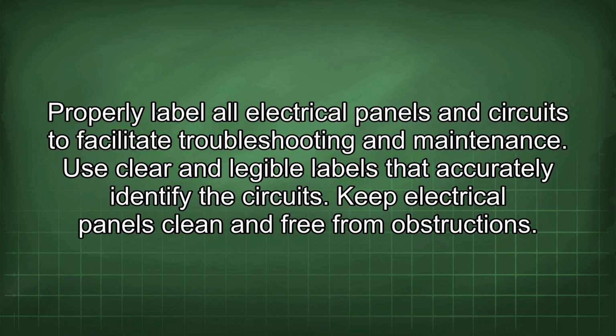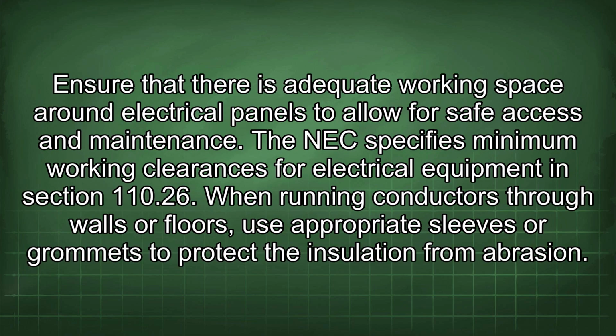Properly label all electrical panels and circuits to facilitate troubleshooting and maintenance. Use clear and legible labels that accurately identify the circuits. Keep electrical panels clean and free from obstructions. Ensure that there is adequate working space around electrical panels to allow for safe access and maintenance. The NEC specifies minimum working clearances for electrical equipment in section 110.26. When running conductors through walls or floors, use appropriate sleeves or grommets to protect the insulation from abrasion.